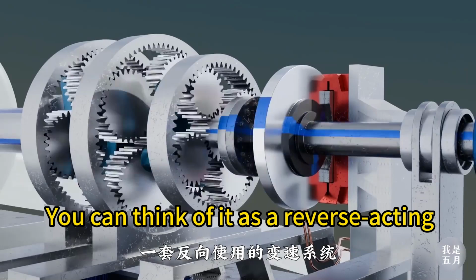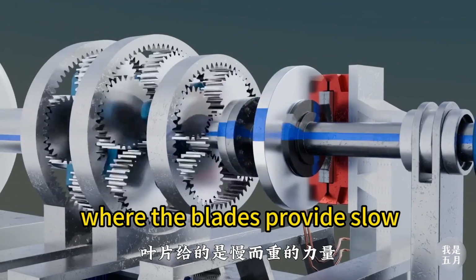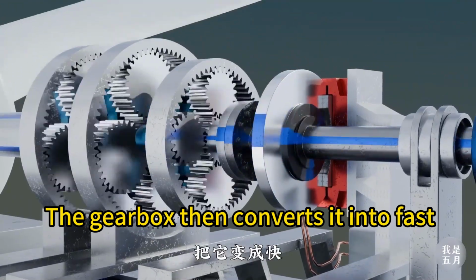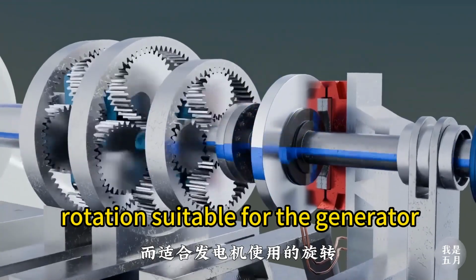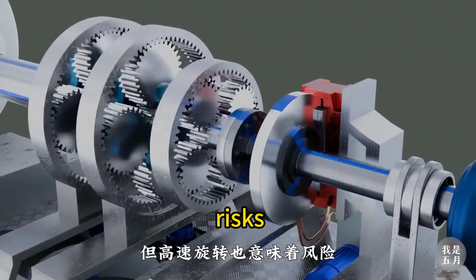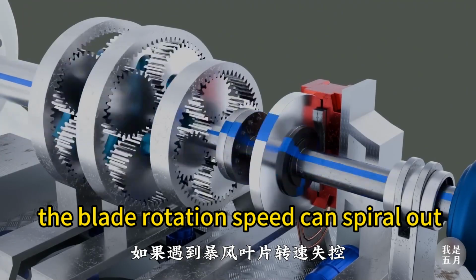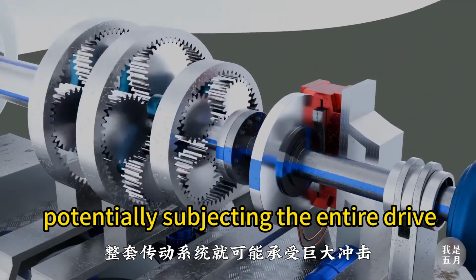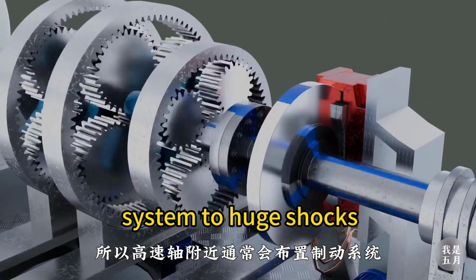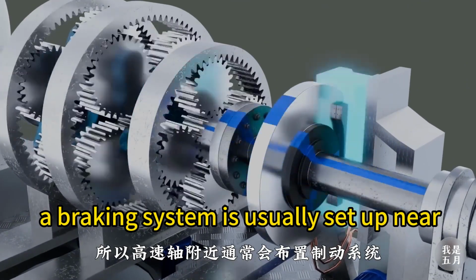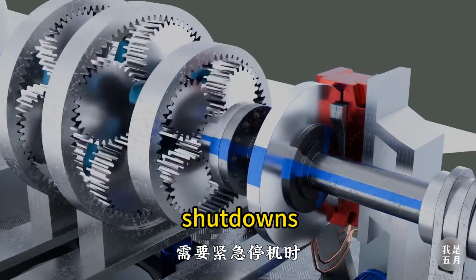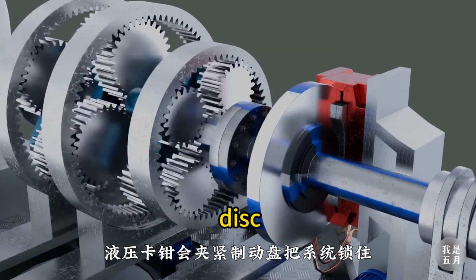You can think of it as a reverse-acting transmission system, where the blades provide slow, heavy power. The gearbox then converts it into fast rotation suitable for the generator, but high-speed rotation also brings risks. If a storm occurs, the blade rotation speed can spiral out of control, potentially subjecting the entire drive system to huge shocks. Therefore, a braking system is usually set up near the high-speed shaft for emergency shutdowns. Hydraulic clamps will tighten the brake disc, locking the system.